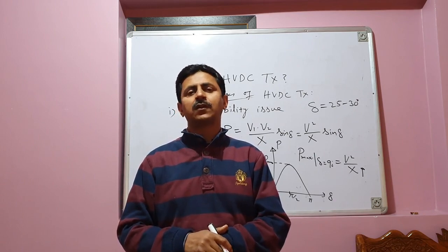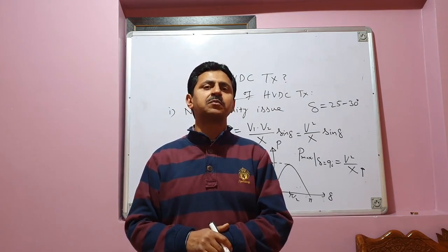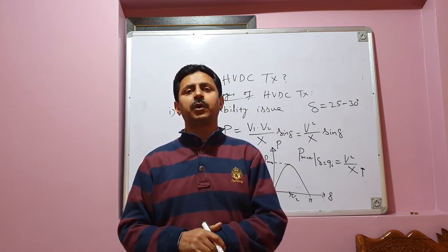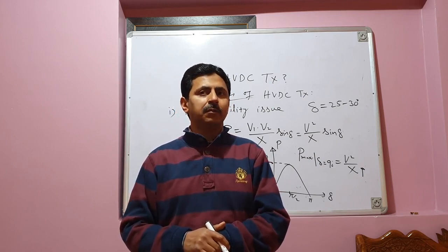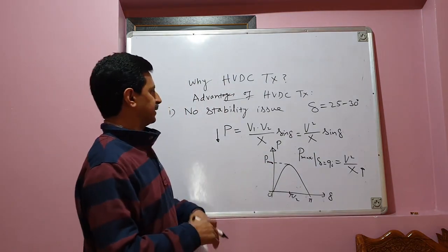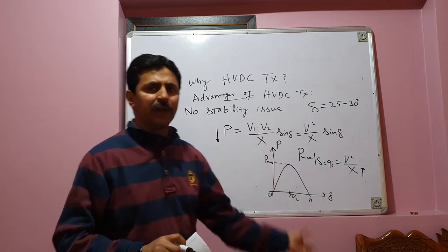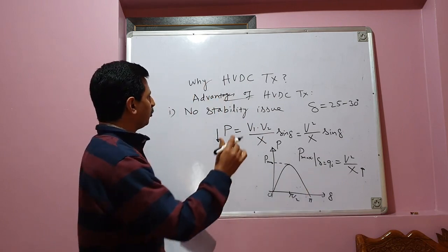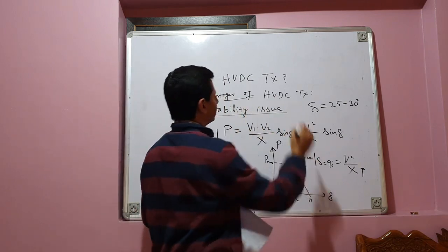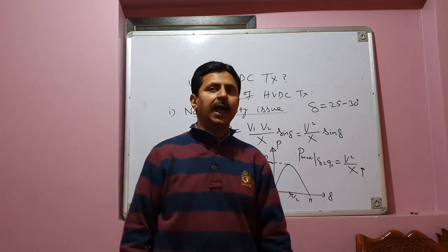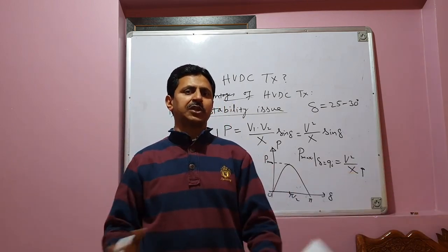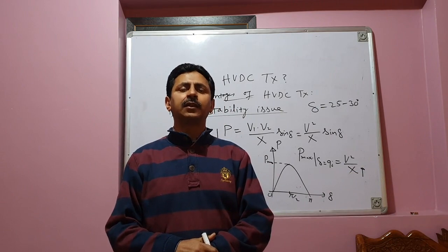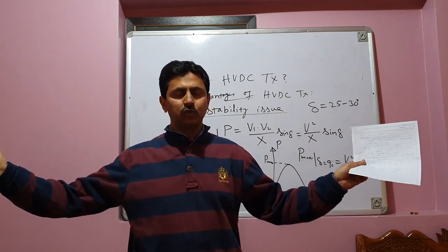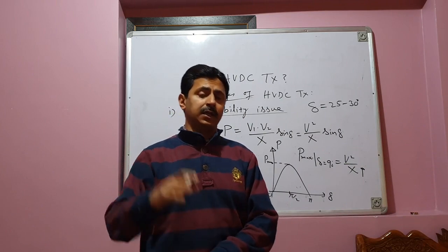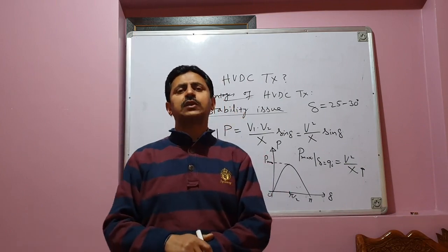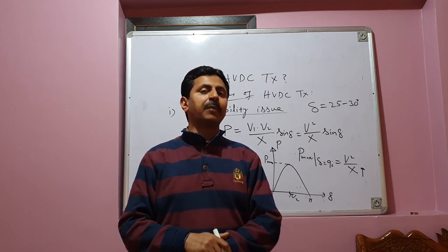This problem does not exist if instead of transmitting the power over AC lines, we transmit the power over high voltage DC lines. Because in HVDC lines, this X term is not there and stability issue is not there. So therefore, in an HVDC transmission system, there is no stability issue, and you can have a very long transmission line. The length of the line, or the distance through which you transmit the power, does not reduce the power transmission capability of the line.